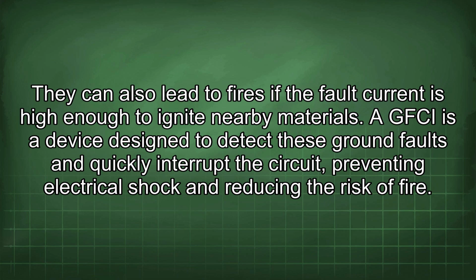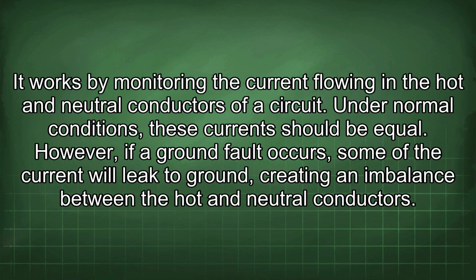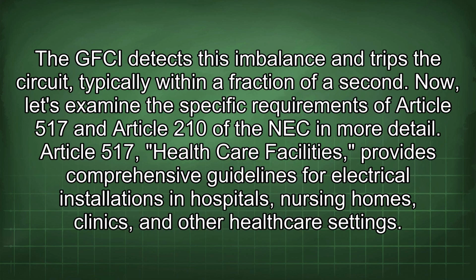A GFCI is a device designed to detect these ground faults and quickly interrupt the circuit, preventing electrical shock and reducing the risk of fire. It works by monitoring the current flowing in the hot and neutral conductors of a circuit. Under normal conditions, these currents should be equal. However, if a ground fault occurs, some of the current will leak to ground, creating an imbalance between the hot and neutral conductors. The GFCI detects this imbalance and trips the circuit, typically within a fraction of a second.